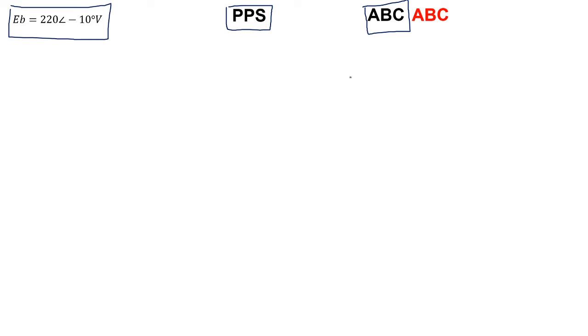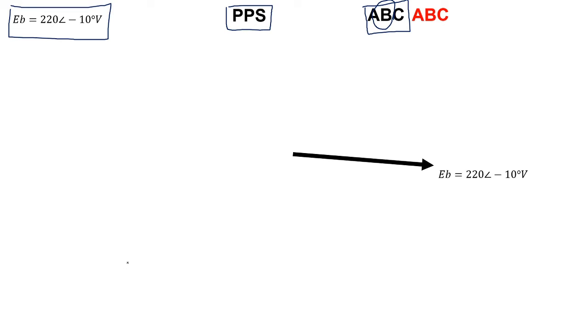Another way to interpret PPS is to say ABC. If my reference changes, I can always move around. For instance, our reference is B, so I start with my reference B at minus 10 degrees. The split between each conductor is 120 degrees. So any time I place the first three vectors, I place them in a clockwise direction. Therefore, I need to subtract 120 degrees every time I move to the next vector.